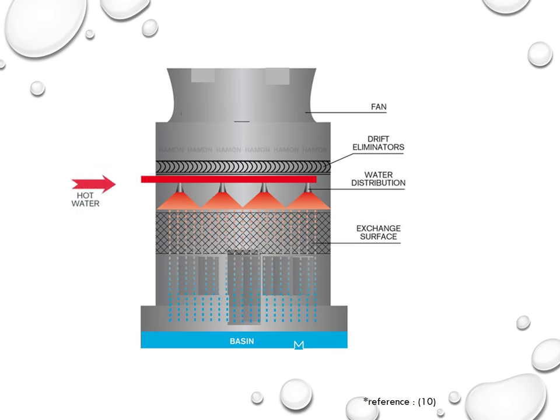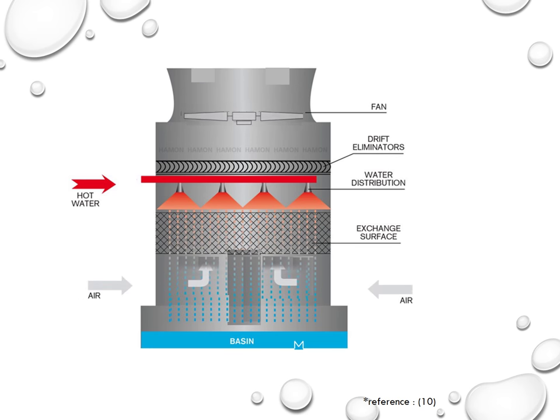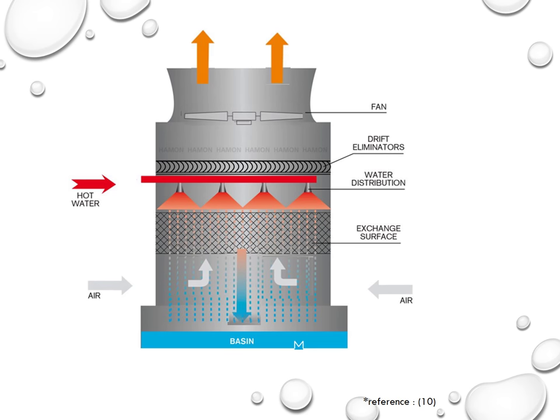Now let us discuss the operation of the cooling tower. The basic operation of an induced draft counter flow cooling tower is very simple. Hot water is distributed evenly by nozzles over the fill media. Air is pulled over the fill area with the help of a fan placed over it. This process results in exposing hot water to the air stream, cooling it by evaporation and sensible cooling. The cold water is then accumulated at the water basin and again used for recirculation.